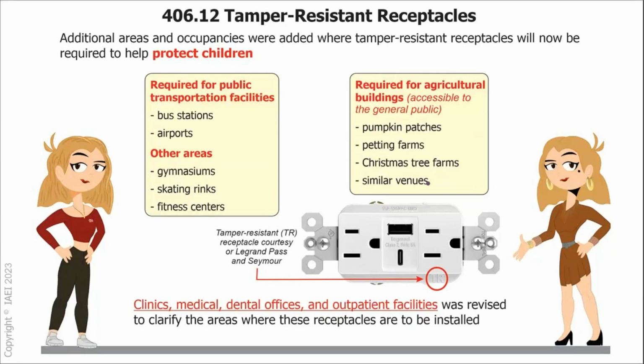And you can see the TR in a tamper-resistant receptacle notated with the TR. If it's outdoor rated, it's going to have a W there, a WTR, for weather resistant, UV resistant. So technically you could not put this in a bubble cover and stick it outside because it's not a weather resistant, tamper resistant plug.